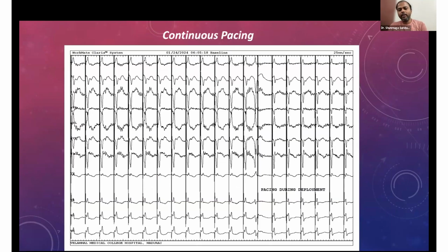If we are not able to provide a rapid rotation, then probably you can go by the second way of delivering the lead by giving continuous rotation. This we more often use for a stylet-driven lead and for left bundle branch pacing ICD leads, where we have to give slow but continuous rotation with pacing. So you have a stylet which can act as a holder for the alligator clip, so that you'll be able to give continuous pacing while doing the rotation.